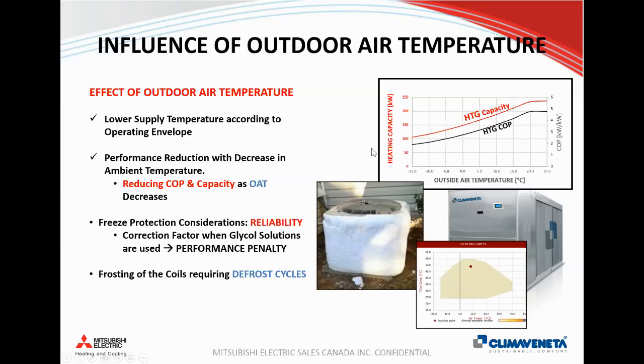With air-to-water heat pumps, you can size them with glycol, but it's important to recognize that there is a little bit of a performance penalty that you are paying, same as in any HVAC system. Glycol solutions inhibit heat transfer, so it usually results in higher pumping heads and a little bit less heat transfer from the system. But there are ways around it. For example, heat tracing is common. And continuous pumping is one strategy that can be employed as well. So typically flowing water will not freeze. So that's one strategy that can be used in combination with heat tracing. But it's all really designer's choice.